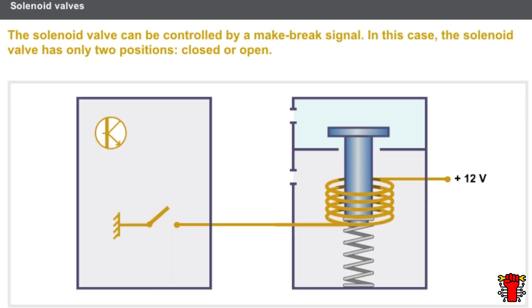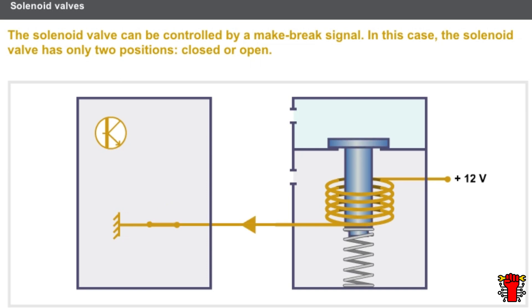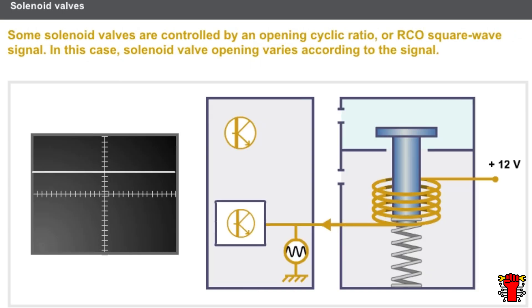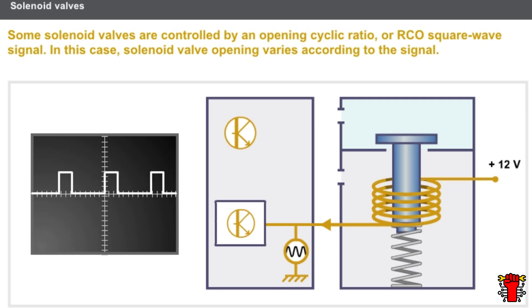There are two ways of controlling the solenoid valve. The solenoid valve can be controlled by a make-break signal. In this case, the solenoid valve has only two positions: closed or open. The solenoid valve can also be controlled by an opening cyclic ratio, or RCO, square wave signal. In this case, solenoid valve opening varies according to the signal.